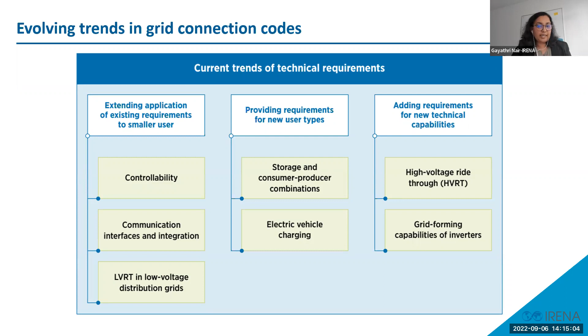Now, to discuss some of them in detail and to give some examples which we have seen in grid codes in the near past: with increasing penetration of VRE and DERs being connected at low voltages, controllability becomes very important. There are two main facets to this. One is to reduce power output and one is to increase power output, and also to return to pre-fault conditions, as demanded by the system operator. So VRE power plants or DERs must be capable of doing this to the extent possible without mandating an additional storage connection. Then LVRT, like I mentioned before, was only mentioned for systems connected to high voltage and medium voltage, but now it is made applicable to DERs that are connected to the low voltage grids as well.